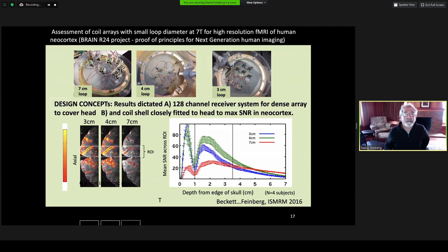I want to talk about the receiver system development. The design concept came from our R24 project, Proof of Principle, where we tested multiple different diameter loops in small eight-channel arrays and found that the three to four centimeter loop diameter gave the highest signal in the cortex beyond the scalp. We wanted to maintain that, so we need to cover the whole brain up to a 128-channel receiver system. It also educated us that the coils need to be very close to the head to get maximum signal in the neocortex.